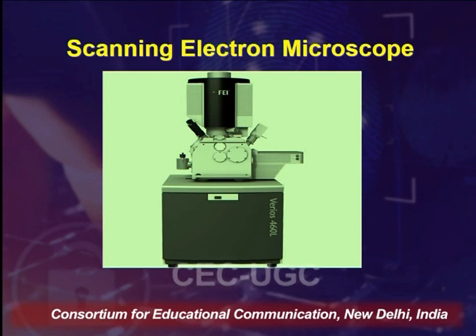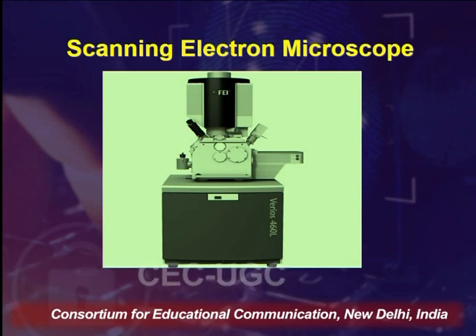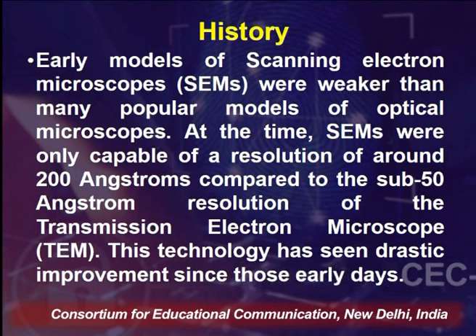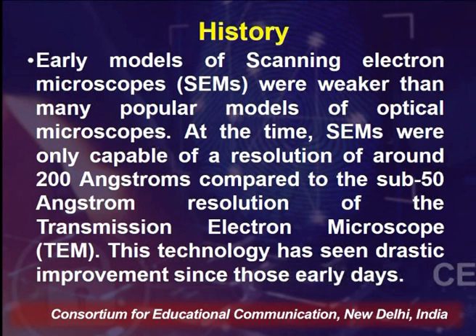This is how a scanning electron microscope looks — it has a vacuum chamber required for the electron gun. Early models of SEM were weaker than many optical microscopes but were capable of resolution of around 200 angstroms, compared to sub-50 angstrom resolution of TEM. With improvements in technology, both SEM and TEM can now magnify images up to thousands of times. The principle of SEM: when an accelerated primary electron strikes the sample, it produces secondary electrons, collected by a positive-charge electron detector, giving a three-dimensional image. TEM produces a 2D image while SEM produces a 3D image.